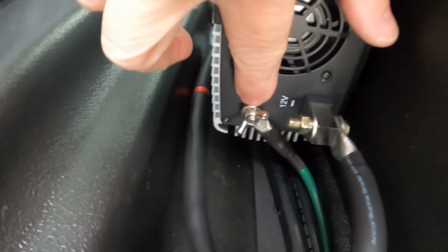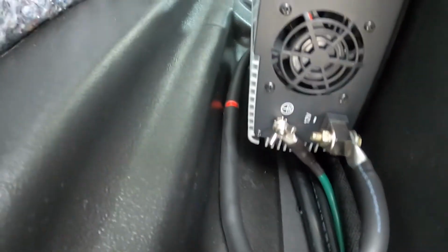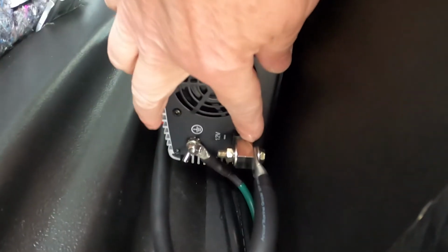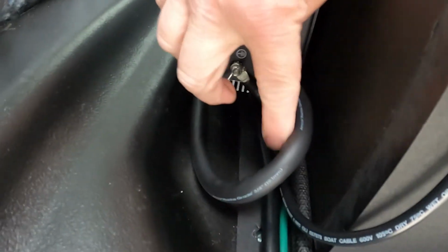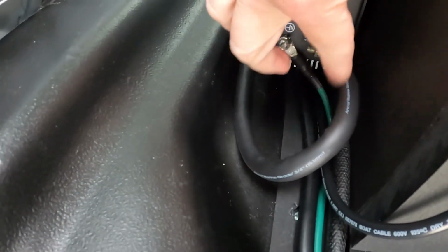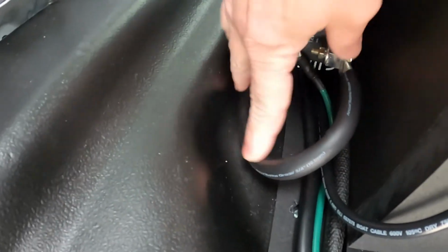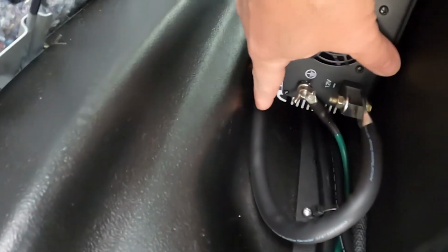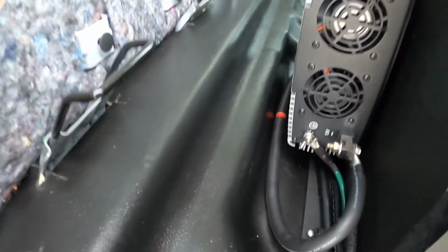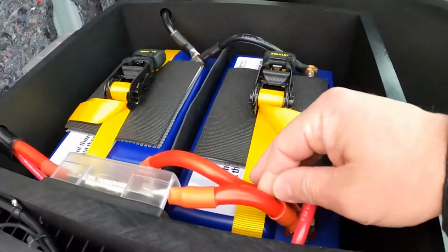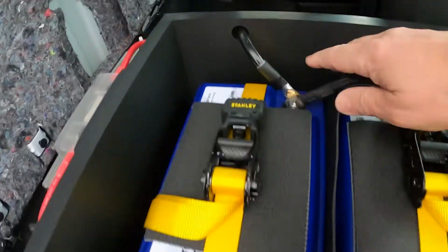This green cable, if I recall correctly, is 8 gauge, which is what the inverter calls for, and I have that terminated on the inverter's chassis ground - this is the inverter's ground here. This cable looks really big, but I put black heat shrink over it because all I had was red cable. This is the 2 gauge recommended by the inverter, and I'm similarly using 2 gauge here to connect the batteries.